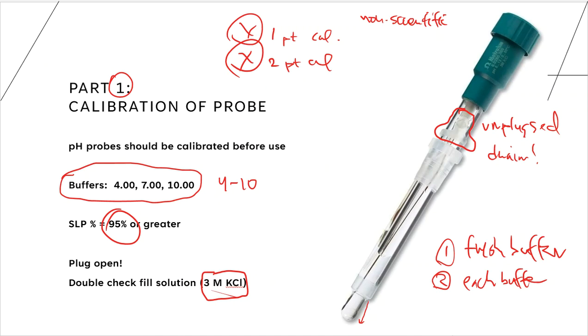All right, so that's part 1 of this lab procedure. We're going to calibrate a probe. We're going to make sure it's plugged after we get finished using it, and we're going to make sure it's unplugged when we use it. And we're going to do 3 buffer calibrations, not a 2, not a 1. And those buffers will be 4, 7, and 10. So it's a very simple process to calibrate a pH probe on our eco titrators. It is meant to be a very simple method. You really don't have to think too much at all.